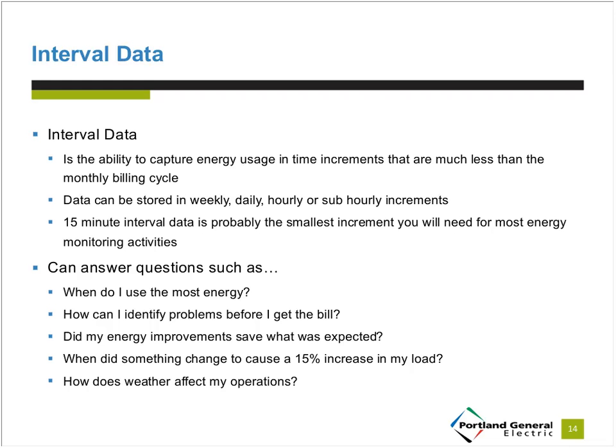It also allows you to look at improvement activities and see what the effects are more immediately, as opposed to looking at your information monthly. And you can look at the loads. If you don't expect any changes and all of a sudden you see a 15% increase in the load, looking at that interval data on a daily or weekly basis, you'll be able to see that change before it has a major impact on your bottom line.